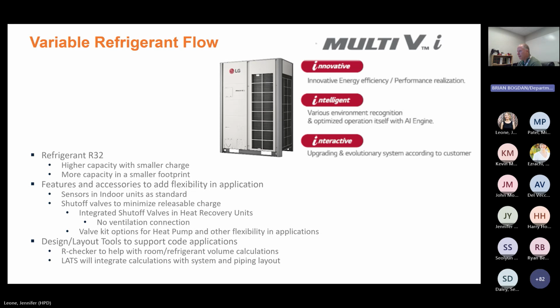We believe this is an important topic, since a lot of the challenges shared earlier involved calculations. I want to clarify that while it was mentioned we're looking at LFL and 19.1 pounds per 1,000 cubic feet as a baseline, it's not as simple as being under that number and being fine. There are plenty of calculations in the ASHRAE 15 standard that help determine how much of the room volume you can take credit for.